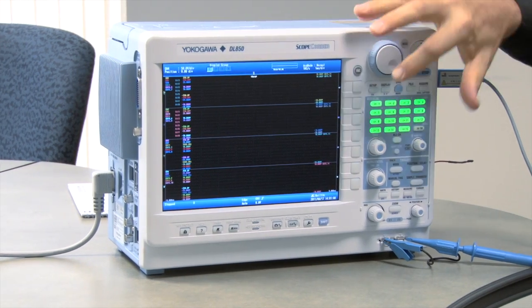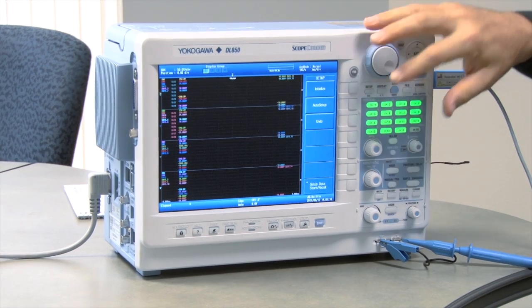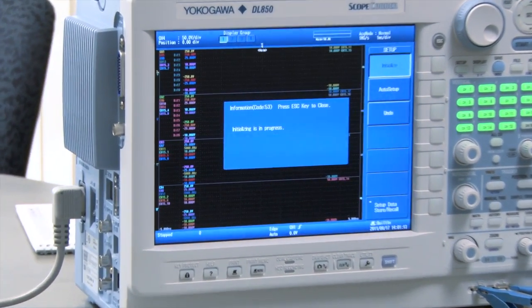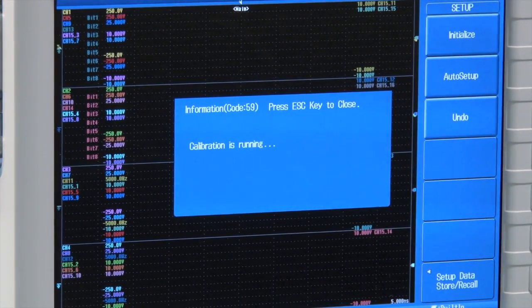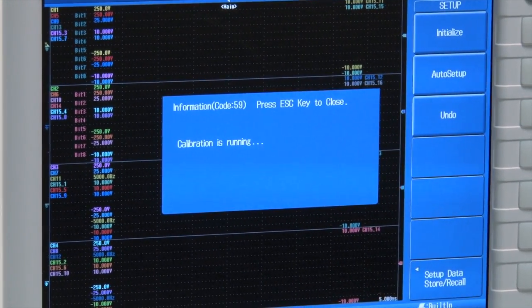The nice feature about the DL850, I'm just going to hit the setup and initialize it because I don't know what condition the product was in before I received it, and then after initialize I'm just going to hit auto setup, and there we are, channel one.